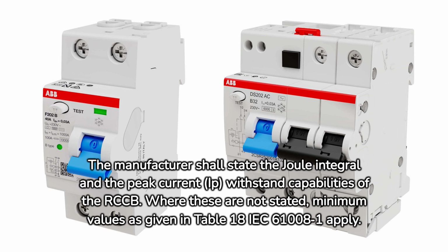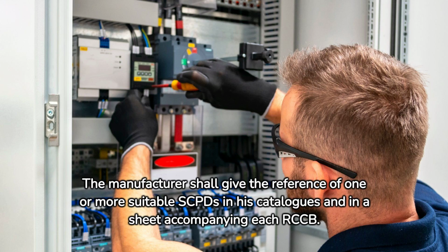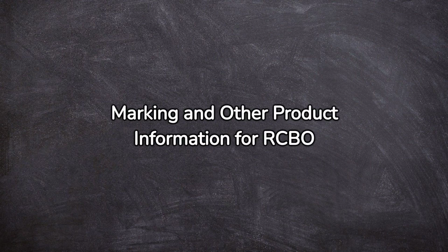The manufacturer shall state the joule integral and the peak current, Ip, withstand capabilities of the RCCB. Where these are not stated, minimum values as given in Table 18 of IEC 61008-1 apply. The manufacturer shall give the reference of one or more suitable SCPDs in his catalogs and in a sheet accompanying each RCCB. Marking and other product information for RCBO.